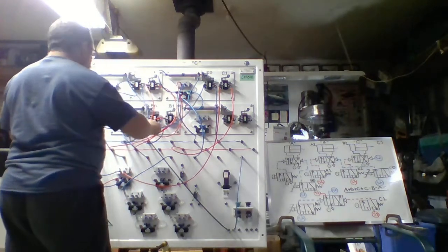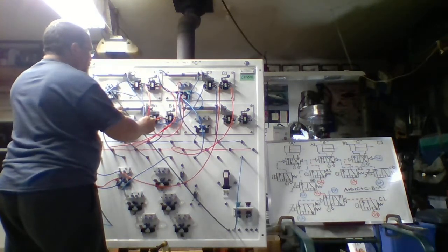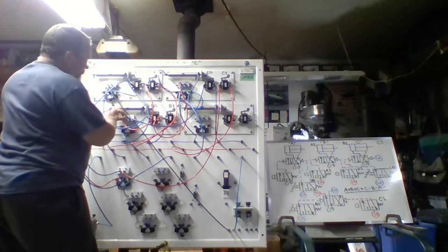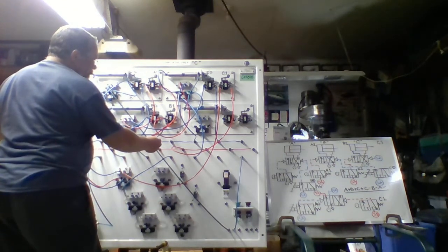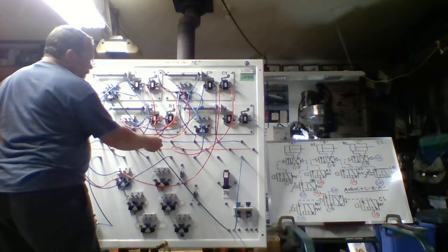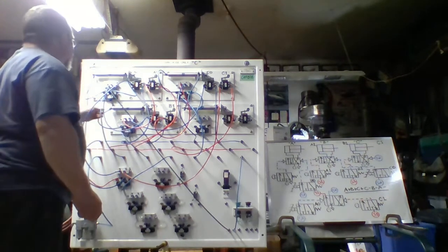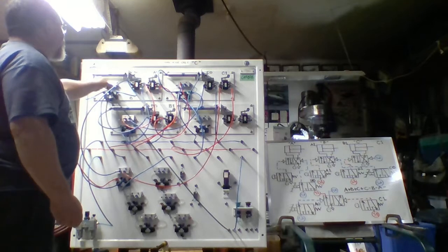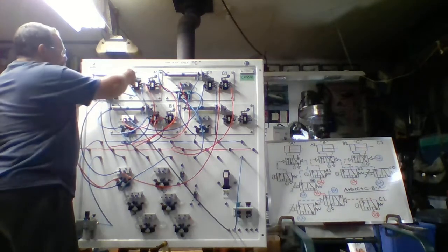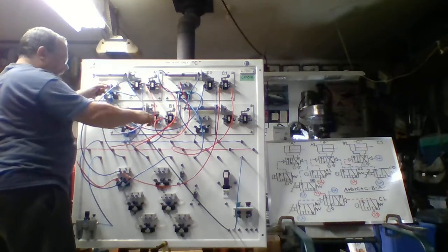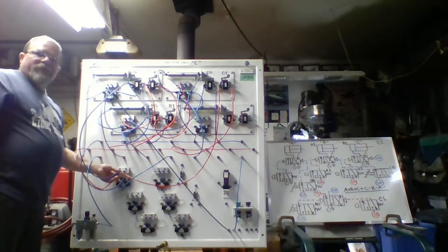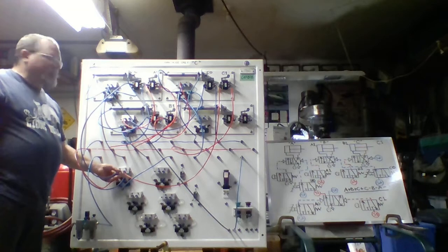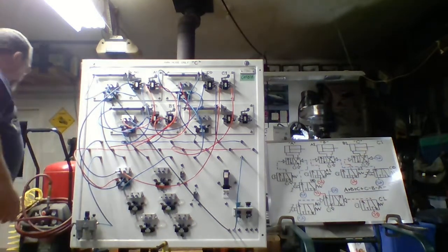You look at the line here, and it's going to pilot for B to shift the 4 two-way valve here and have B retract. And that, of course, gets on B0. We're supplying that with source 2 as well. When we do that, we're going to pilot here for A to retract. Once we do that, of course, we're on A0, again supplied by source 2. And here's our line coming down to my cascade valve. We're right back to the beginning. We're ready to start over. We're at source 1, everything's back in the home position.